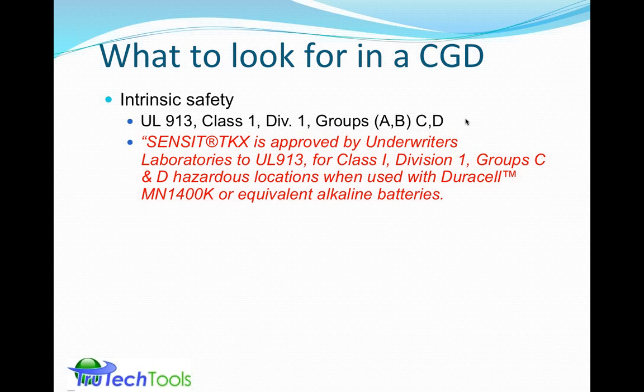But it also says, when used with Duracell MN1400K or equivalent alkaline batteries, here's where used as intended is part of your obligation as the end user to maintain the intrinsic safety. You can't use a different battery and still have it comply with that. They've tested to be sure. They know there's a repeatability to the manufacturing construction of those Duracell batteries, such that that's the way they want it to be used. And that's the part where you have to make sure you're using it correctly in order to achieve and maintain the intrinsic safety.